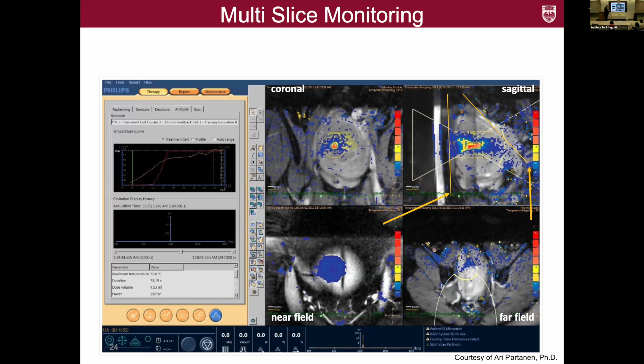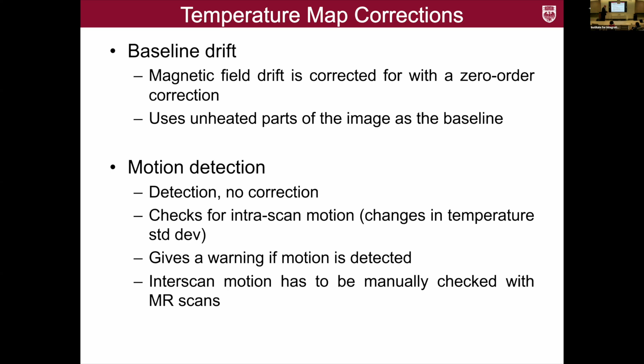Problems are, of course, that there might be a baseline drift. The magnetic field drifts over time, so it's not permanently stable, and you have to do some corrections. And there's also motion. The patient motion is maybe the most important. So we have to be very careful that the machine is set up. If the patient moves too much, the scanning will be interrupted and the treatment will be interrupted.